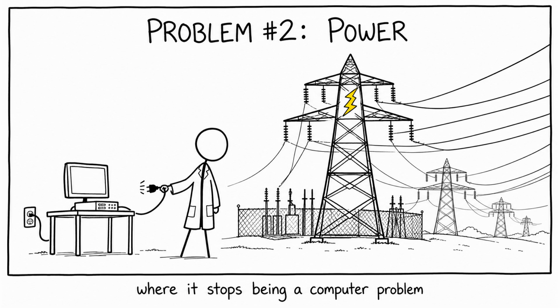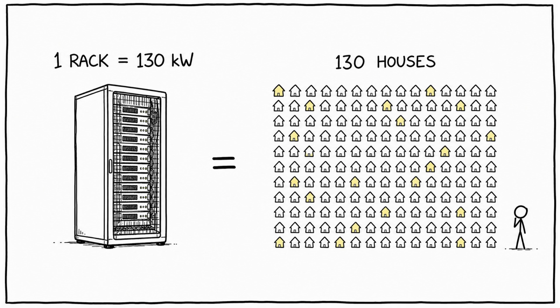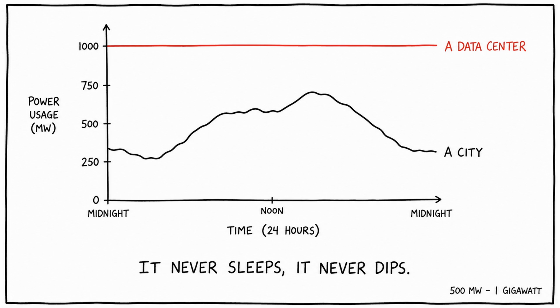Second, power. This is where it stops being a computer problem and starts being an infrastructure problem. That single $3 million rack draws about 130 kilowatts. An average house draws about 1. So one rack is roughly 130 homes, humming away in a metal box. A large campus wants 500 megawatts to a full gigawatt. That is a small city, except a city's demand rises and falls all day. A data center just pulls flat out, forever.